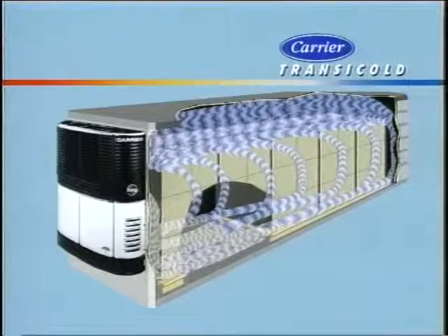If an abnormal condition is sensed, an alarm is automatically registered in the message center. The unit may or may not shut down depending on what the alarm is. Less critical alarms will not let the unit shut down, and the message center will show check at next service interval instead of status OK. Shutdown alarms, such as high discharge pressure, will cause the unit to shut down. Should this occur, the message center will show unit shutdown, see alarm list.